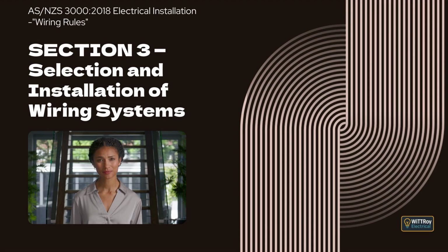Clause 3.3.2.8 Other mechanical stresses. This clause explains that wiring systems must be selected and installed to minimize damage to insulation, sheathing, and connections during installation, operation, and maintenance. Measures may include providing adequate supports at suitable intervals, using fixings that hold the cable without damage, using connections that reduce strain at joints and terminations, observing minimum bending radius limits, and allowing flexibility to accommodate movement or tension.